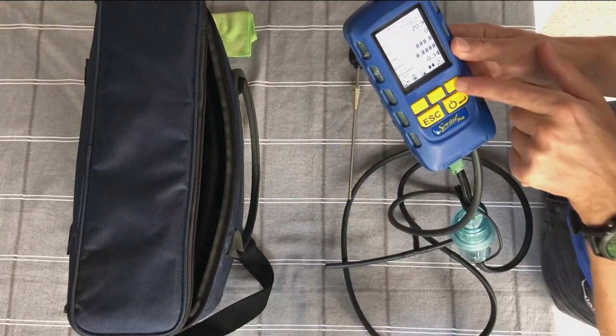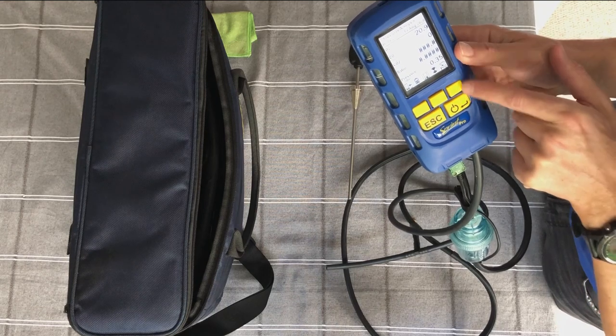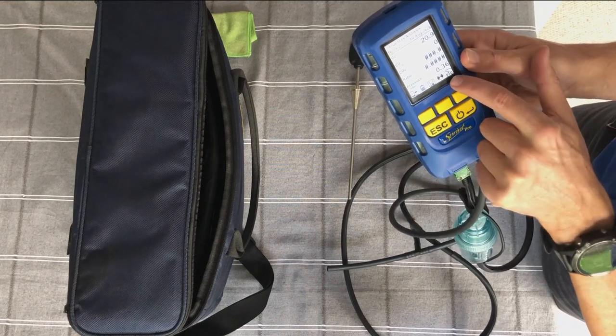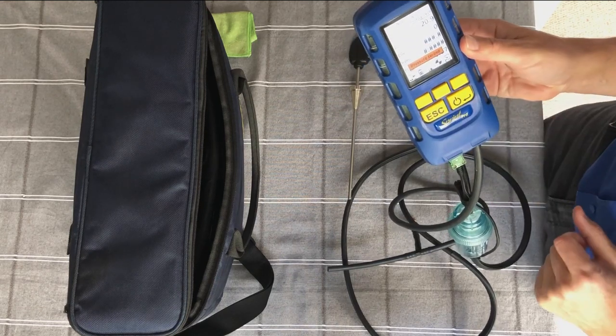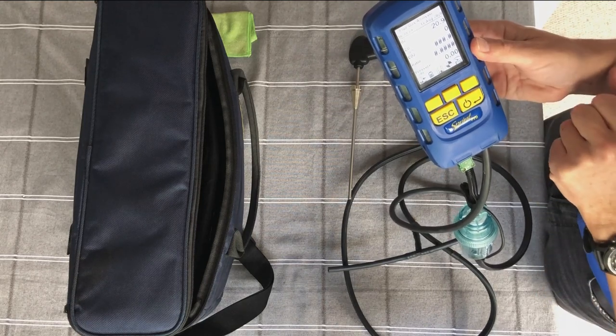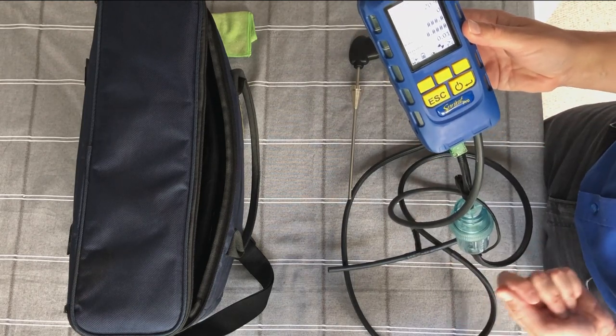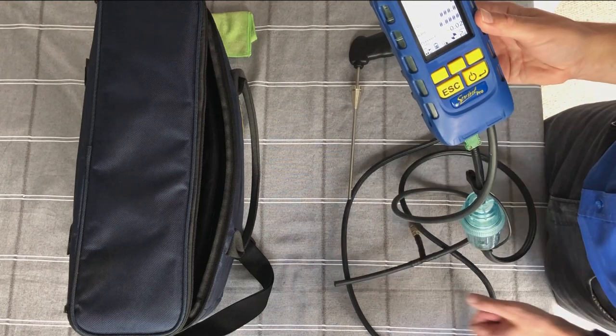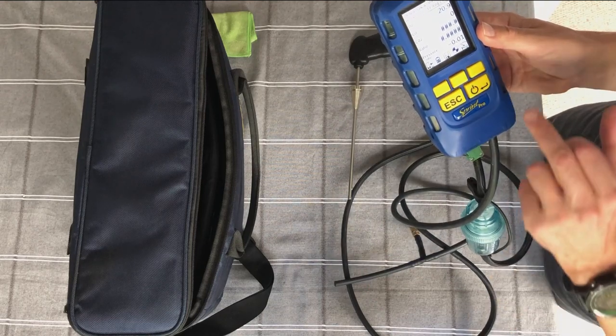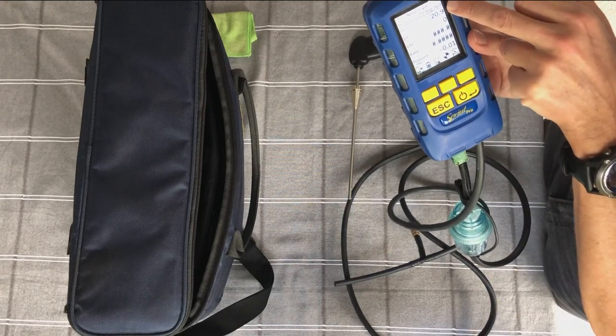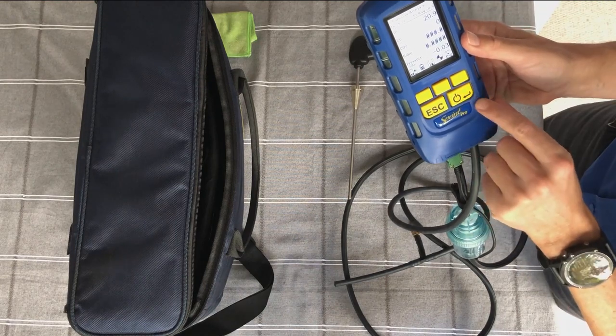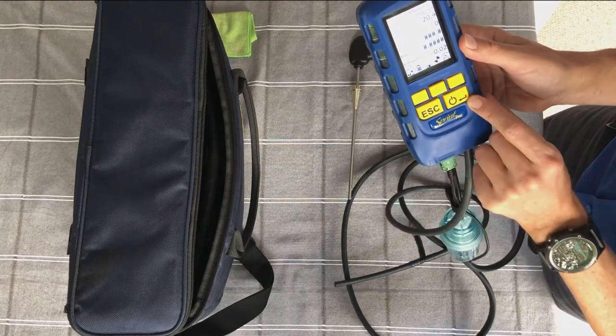And that button, remember the button corresponds to the yellow button below it. So that's pressure equals zero. So if I want to zero my pressure, I can do that so that I know I'm zeroing my pressure before I start taking any pressure measurements. This number one means it's page one. So if I press the enter button, it'll scroll through the pages.